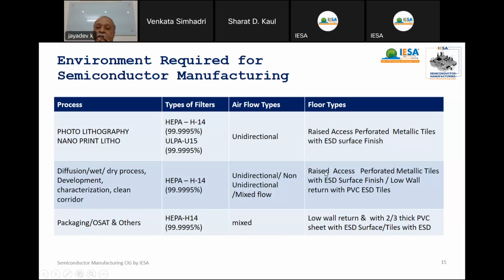In photolitho as well as the diffusion process, we use raised access perforated flooring. In other cases, the return can be a low wall return with PVC type. Low wall means the supply comes from the top. So all along the periphery of the wall, about 200 mm to 300 mm above the floor, return air goes back into the AHU through the return air risers. In some cases, the flooring may be ESD tiles, 600 by 600, again with ESD control of 10 to the power 5 to 10 to the power 7 ohm centimeter. For packaging and other applications, it is a mixed flow. Air comes from the top, moves all along the wall like a piston flow, and then goes back to the AHU. And here we can use PVC ESD tiles or sheets 2 to 3 mm thick with ESD control.